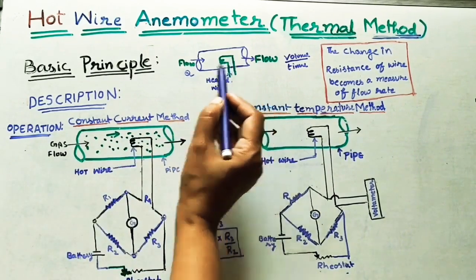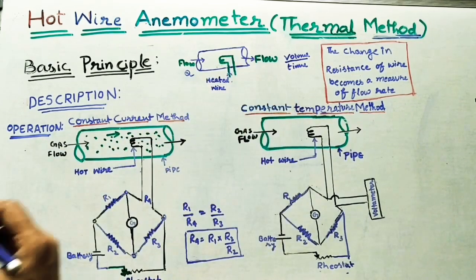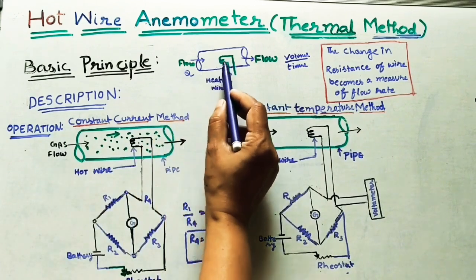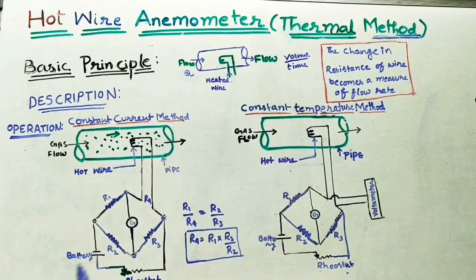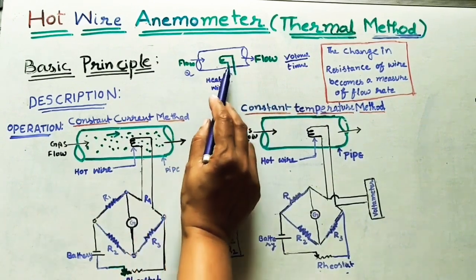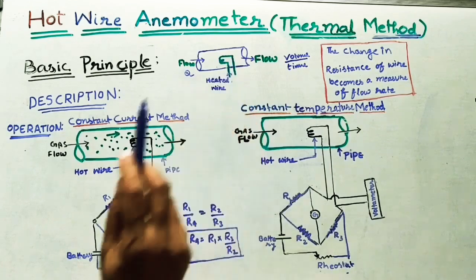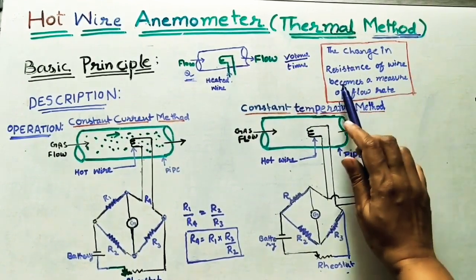Initially the wire temperature is high because of the heat we are supplying to it. During the flow, the flow temperature is less, so it will absorb heat from the filament. After absorbing the temperature, the flow gets heat and the wire gets cool — its temperature becomes less. Because of this lower temperature, the resistance of the wire will also change, since temperature and resistance depend on each other. That change in resistance will find the flow, and becomes a measure of flow rate.